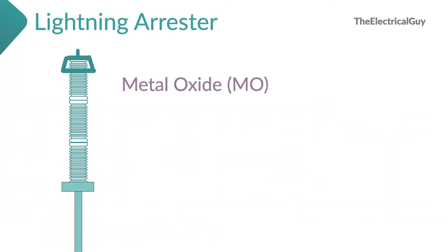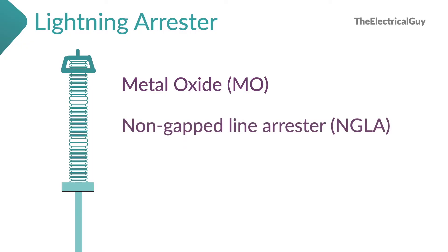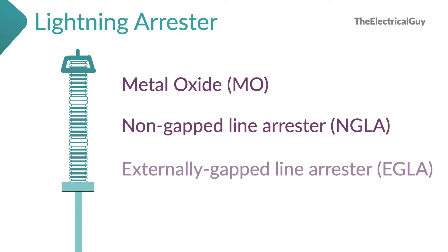For substation applications, metal oxide (MO) surge arrestors without gaps have been state of the art since the late 1980s. For transmission lines, non-gapped line arrestors (NGLA) and externally-gapped line arrestors (EGLA) are used.